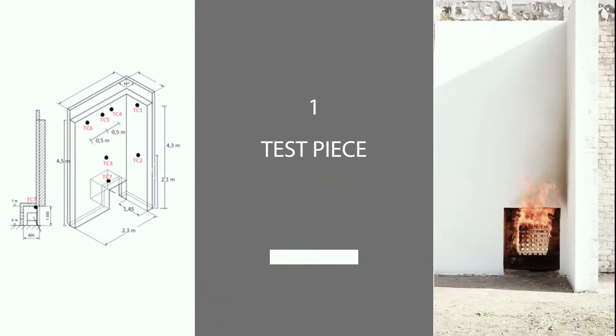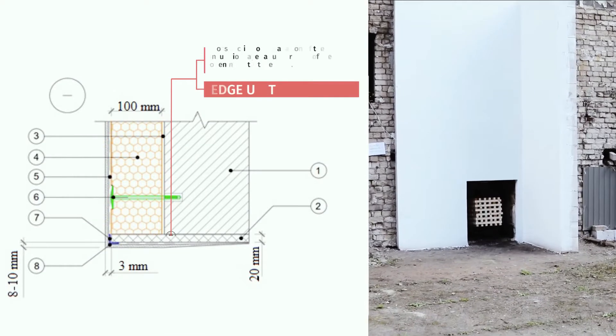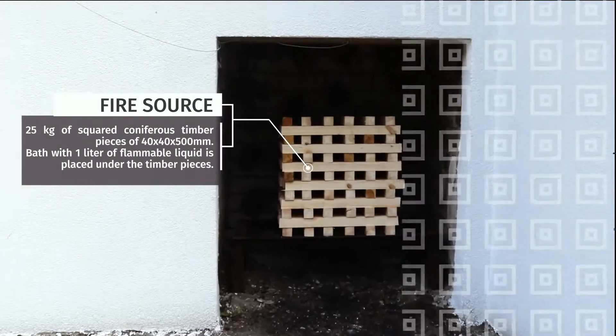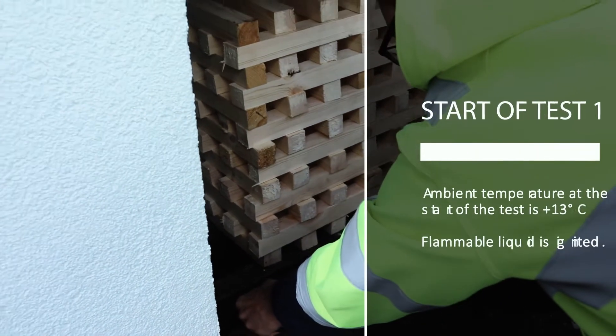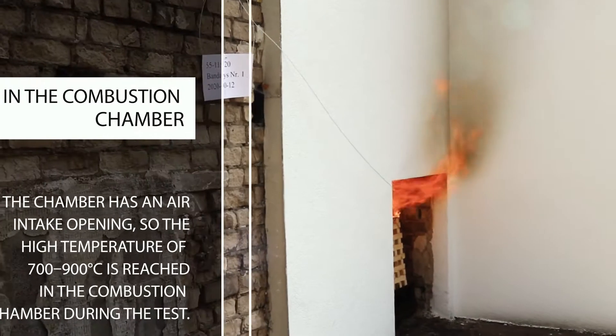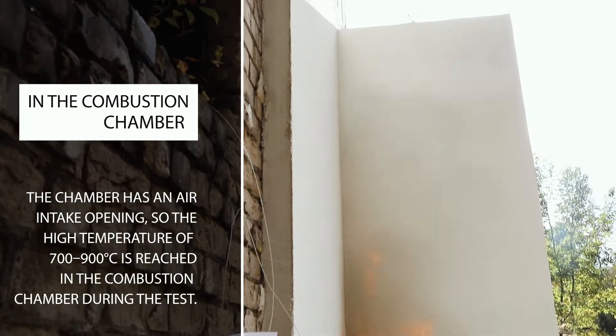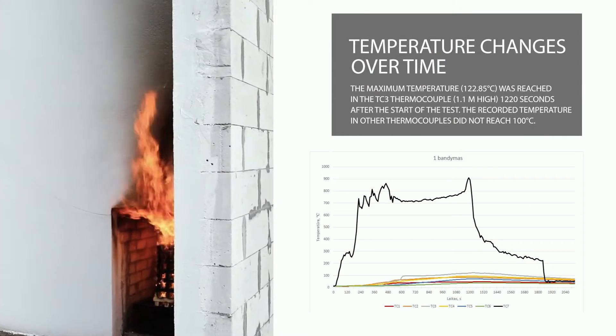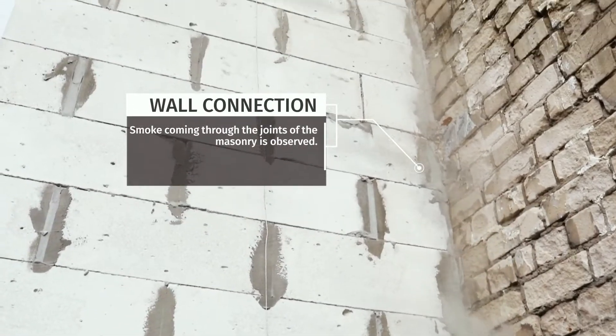First test piece. The cross section of the thermal insulation layer at the upper edge of the opening of test specimen number 1 is shown. The fire is produced by 25 kg of coniferous timber, with flammable liquid ignited at the beginning of the test. Ambient temperature is +13°C. The combustion chamber has an air intake, so the temperature in the chamber reaches 700 to 900°C during the test. The diagram shows that the maximum temperature, exceeding 122°C, is reached in thermocouple TC3 about 20 minutes after the start of the test.